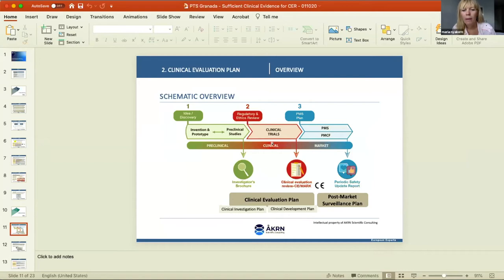Take the information from your investigator brochure and put it as part of your clinical evaluation plan, or CEP. Then you bring in your clinical investigation, your CIP, which is your clinical investigation plan, previously called protocol. It's basically what you launch at the clinical sites or hospitals, deciding how you want to run your clinical trial there. Then you also include your post-market phase.